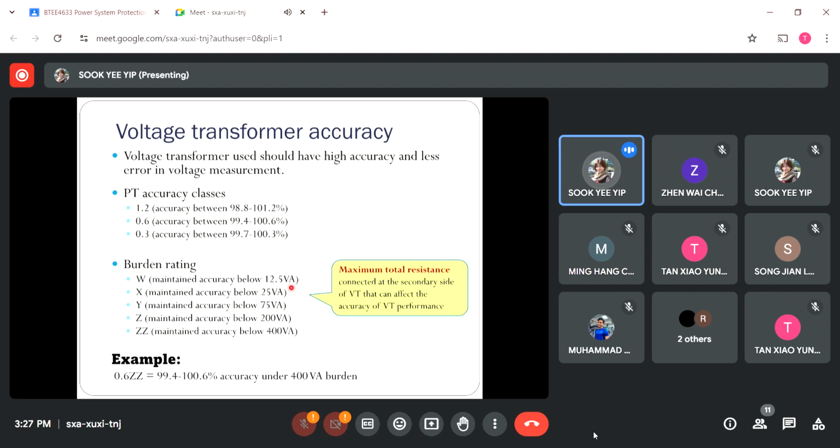So what volt-ampere says is the apparent power, a unit for the burdens, all right? So if you're able to keep the secondary side with the burdens lesser than 12.5 volt-ampere, we are able to get accurate measurements of voltage. The next one in line here, let's say we choose the one with X as the burdens rating. It can give us accurate transformations of the voltage.